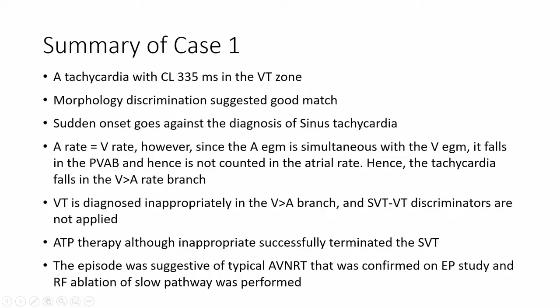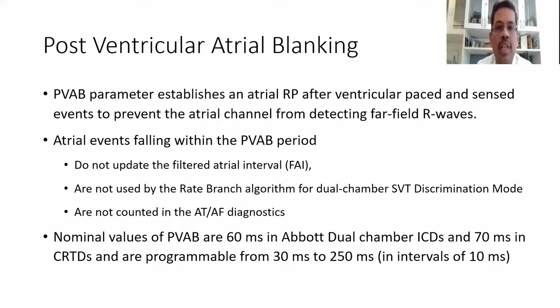A word about post-ventricular atrial blanking. It's a parameter that establishes an atrial refractory period after a ventricular paced and sensed events to prevent the atrial channel from detecting the far field R waves. Atrial events falling within the PVAB period do not update the filtered atrial interval, are not used by the rate branch algorithm for dual chamber SVT discrimination mode, and are not counted in the AT/AF diagnostics. So this is one of the situations where the ICD devices may not be able to look at the atrial EGMs, and if all EGMs fall in this period, this becomes a problem. The nominal values of PVAB are 60 milliseconds in the dual chamber ICDs and 70 milliseconds in CRTDs, but can be programmed anywhere from 30 milliseconds to 250 milliseconds in intervals of 10 milliseconds.